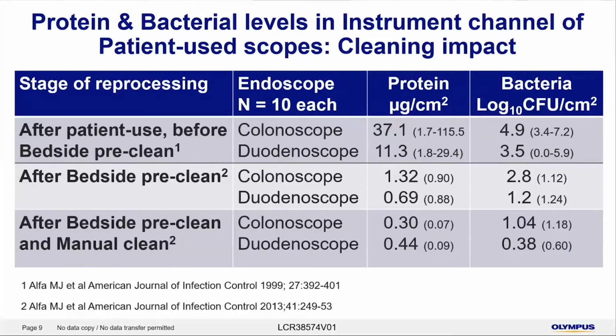area. These were 10 clinically used endoscopes, so of course, depending on the procedure and the duration, the data will vary somewhat in terms of the amount of material on them. But I'm presenting the data for the colonoscope and duodenoscope. If you look at the protein in micrograms per centimeter squared, you'll see that the average from those 10 clinical procedures for colonoscopes was 37 micrograms per centimeter squared, and for duodenoscopes was 11.3. But in both instances, the data to the right in parentheses shows you the range. And the range can go as high as 115 micrograms per centimeter squared.